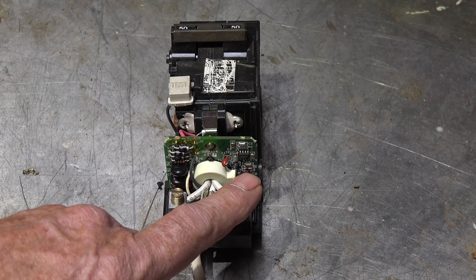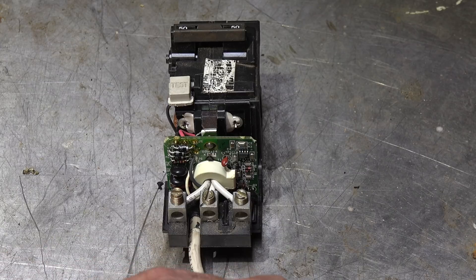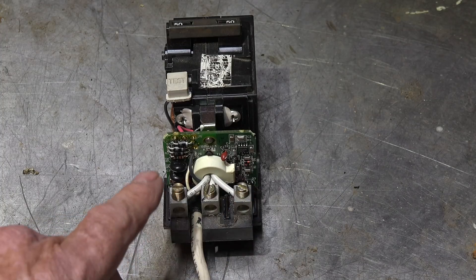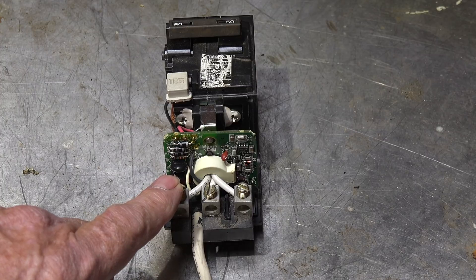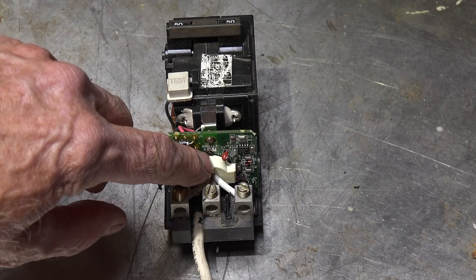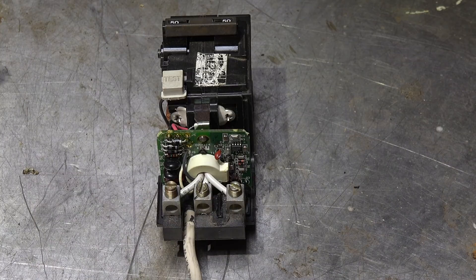...but the controls, the timers, and so on might run at 120 volts. So one hot lead carries power out and comes back through this neutral. This neutral wire goes to the neutral lugs on the main panel. Now if I had 10 amps on each hot leg through the element, but then 1 amp going through the controls, I'd have an unbalanced circuit and the ground fault would kick off.